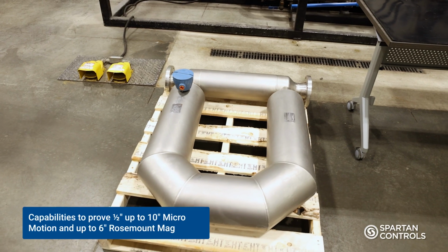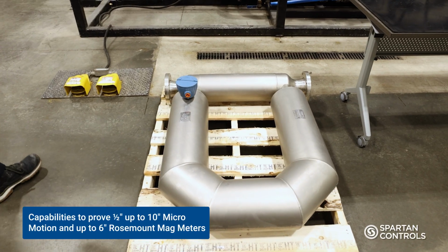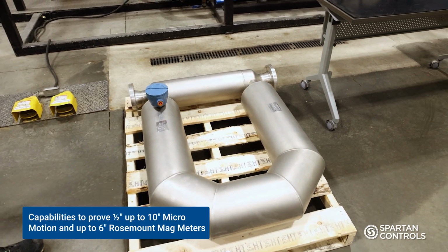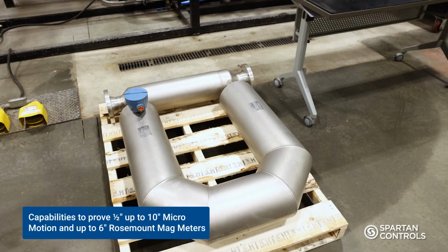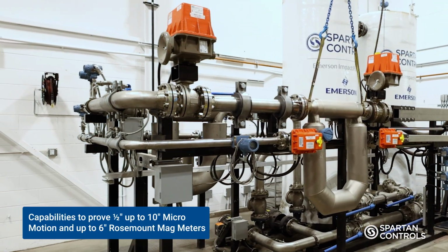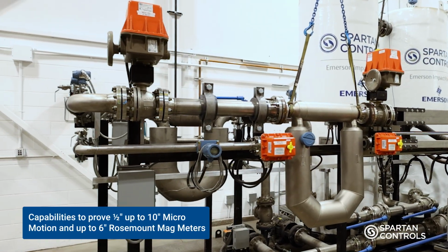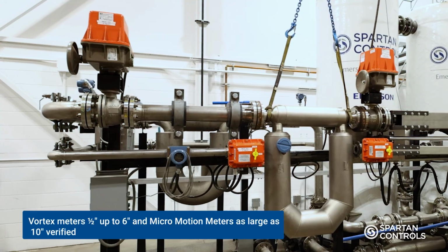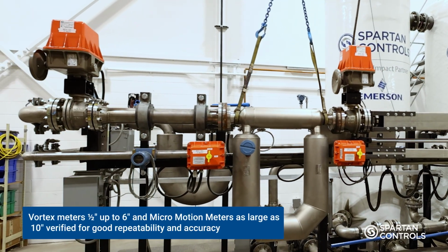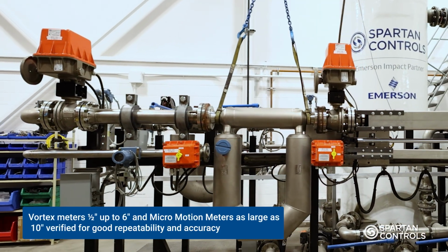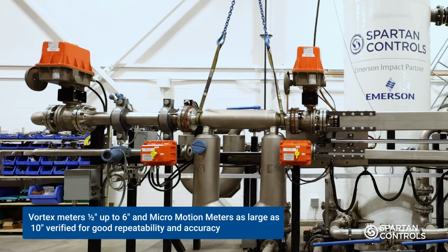The stand has capabilities to prove half-inch all the way up to 10-inch Micro Motion meters, and up to 6-inch Rosemount mag meters, to within their published factory specifications. Additionally, vortex meters from half-inch to 6-inch can be verified for good repeatability and accuracy.